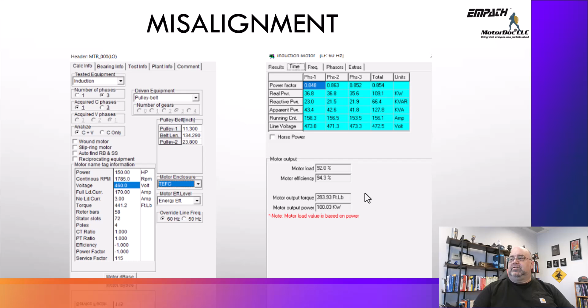If I exceed the losses in the machine when I'm coming up with a calculation, because some folks out there are doing that, it can't be real. So if I'm being told a 1 horsepower motor, which is 0.746 kilowatts, is somehow using 20,000 kilowatt hours worth of energy, fully loaded times 8,760 hours, that nowhere comes near 20,000 kilowatt hours. So if somebody tries to tell me at a conference, and this has been repeated a couple of times, oh yeah, this little 1 horsepower motor with a noisy bearing is doing 20,000 kilowatt hours a year, run away. So in this particular case, this belt is slipping by about 11.5%.